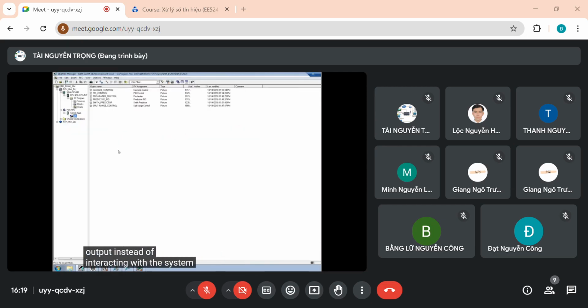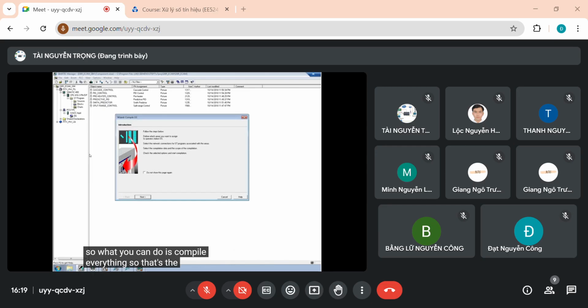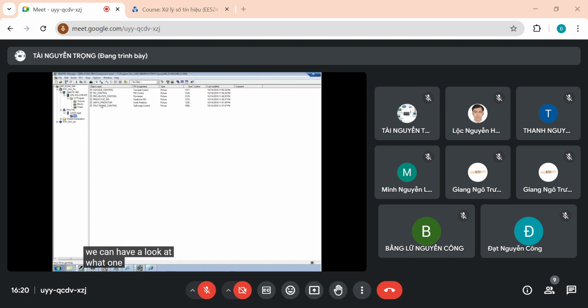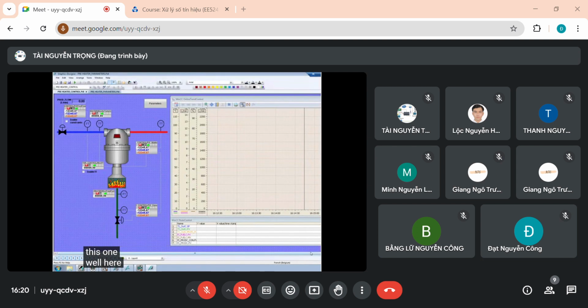Instead of interacting with the system using CFC, what you can do is also design your human-machine interface. And for Siemens, this is done using WinCC, so the Windows Control Center. So what you can do is compile everything so that the variables become available in the WinCC Control Center. And what you can then do is design pictures of the type that you see over here to generate a nice human-machine interface. So we will stop this because this will take too much time. We can have a look at one of these images, for instance this one. Or here you can design your interface with the actual system, so the human-machine interface. Here it seems it's done using the graphics designer that is associated to the Windows Control Center WinCC.